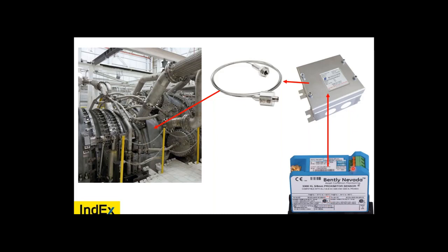It must always go into a junction box. I've had people fight this all the time. This must go into a junction box. And just because this says it's EXIA or something like that, that doesn't mean it's only EXIA. You have to consider the circuit, EXNL or IC circuits, the complete system. You have to consider all of this at the same time.